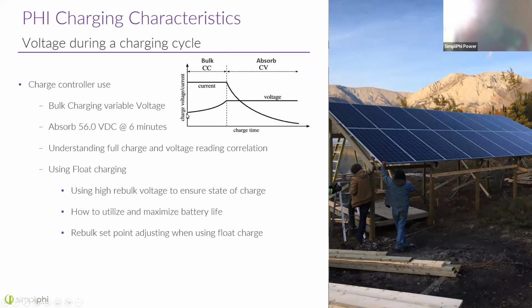As that constant current is being pushed into the battery, as the battery starts to fill up, the charge controller has to apply more voltage to push that current in at the same rate. So you can see in the bottom part of the graph that the voltage is increasing as the current remains constant. It keeps increasing until we hit a set point of the charge controller. And that set point is the absorb voltage.